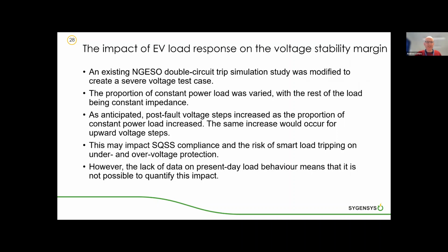So looking at the voltage stability margin, ESO helped us with a study case modifying it to produce a severe voltage test case. We then applied varying amounts of constant power load, with the rest of the load being constant impedance. And as anticipated, the post-fault voltage steps increased as a proportion of constant power load increased. And we were looking at voltage steps down, but voltage steps up would also increase with higher percentage of constant power loads. So this may affect SQSS compliance, and then also the risk of smart loads tripping on either under or over voltage protection. But the lack of data on the present day characteristic loads means it's hard to say by how much that risk will be increased in the future.